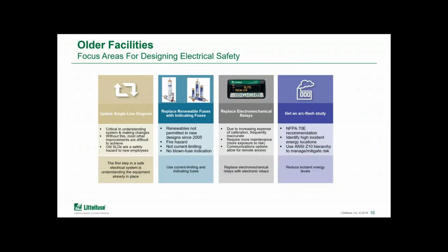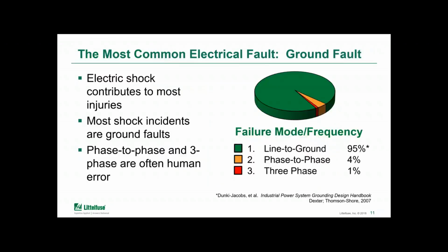Now, hopefully, a lot of the facilities that you work with have been able to do an arc flash study, and if not, it's certainly strongly recommended. In some regions, those are actually required as well. But that arc flash study really helps to identify the high-risk areas. So the results of that study are then used as a ground zero point to start managing the risks using the hierarchy of controls that we've just spoken about.